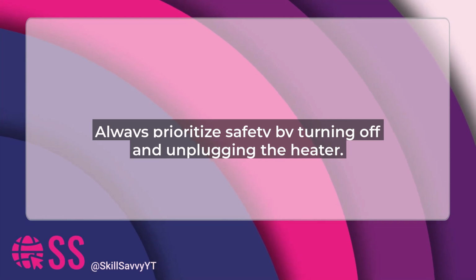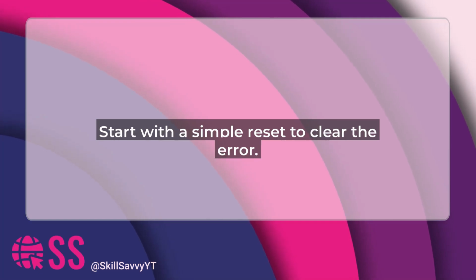First off, let's quickly understand what error code 99 means. It typically signals a problem with the ignition system, possibly due to gas supply issues, a faulty sensor, or even simple power glitches. Safety is our top priority, so before you start, make sure to turn off the heater, unplug it from the power source, and if it's gas-powered, ensure there's no gas leak by checking for any unusual smells.